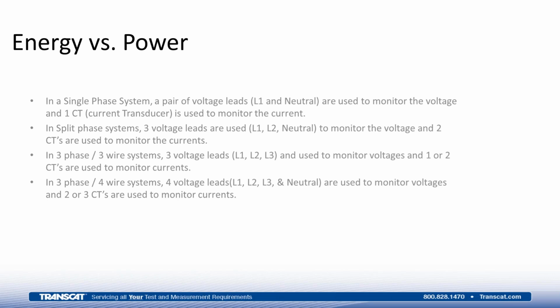Now, in our larger commercial and most of our industrial systems, we're going to use what are referred to as 3-phase, 3-wire, or 3-phase, 4-wire systems. I don't want to confuse you too much with this. I just want you to know that in those cases, we would potentially need 3 voltage leads to connect up to the 3 phases, L1, L2, and L3. And we would use a couple of CTs to monitor the currents in the 3-phase, 3-wire system.